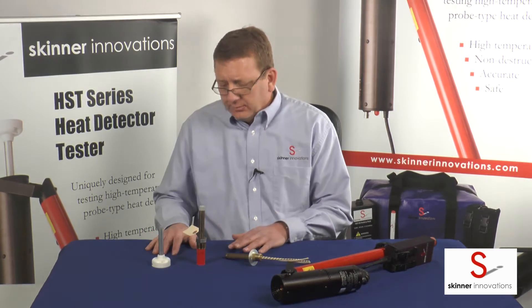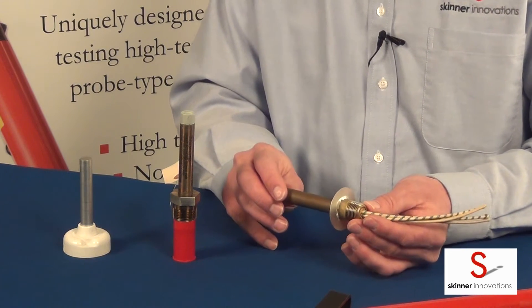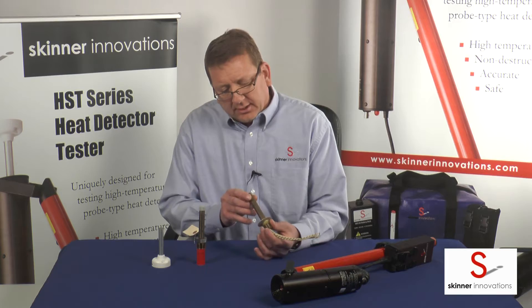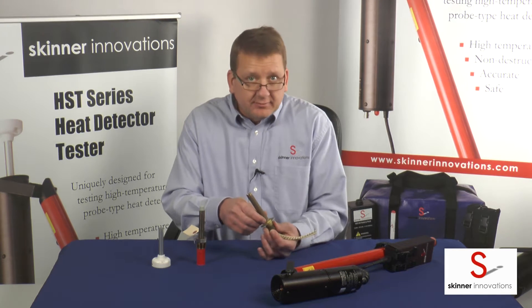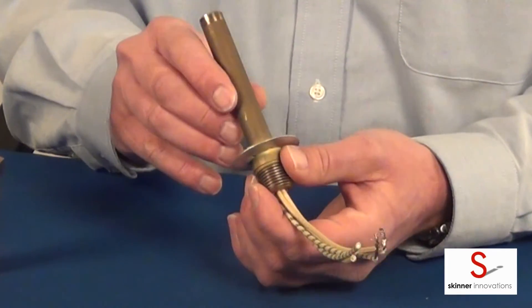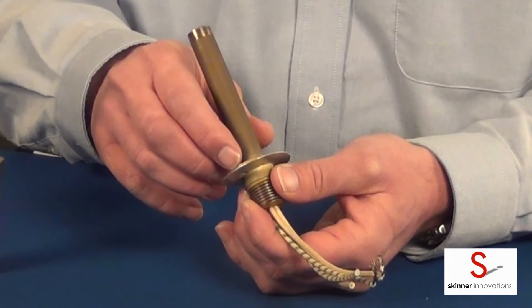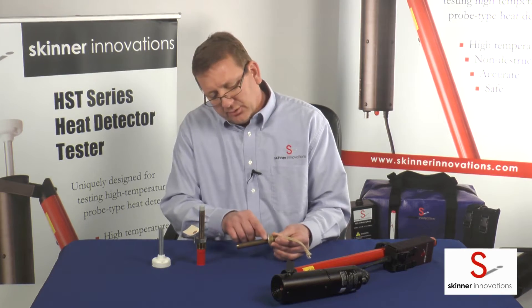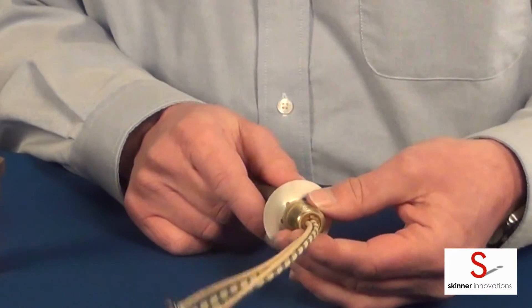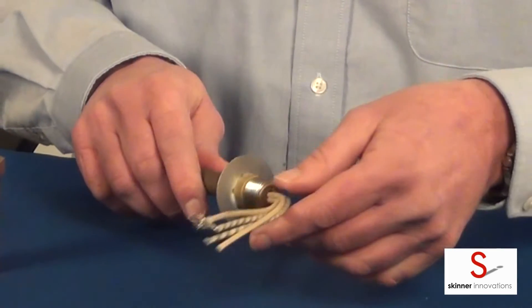In front of me I have three detectors. The first one I'm going to show you is a Fenwall DAF, Fenwall Detect-A-Fire Detector. I can tell it's Fenwal because stamped onto the bottom of the wrenching flat here it says Fenwal. The model or series is also stamped on the bottom — it says 27-121. The detector set point you'll find right on one of the wrenching flats here. This one says 725°F, meaning it's a 725 degree detector.